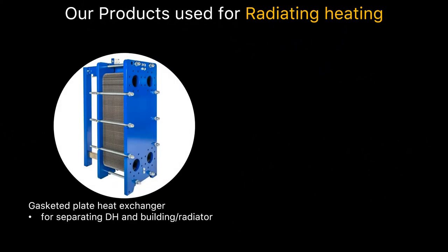We use a gasketed plate heat exchanger when the water can be fouled, for instance when chalk or something else is in the water. This gasketed plate heat exchanger is openable and can be cleaned easily.